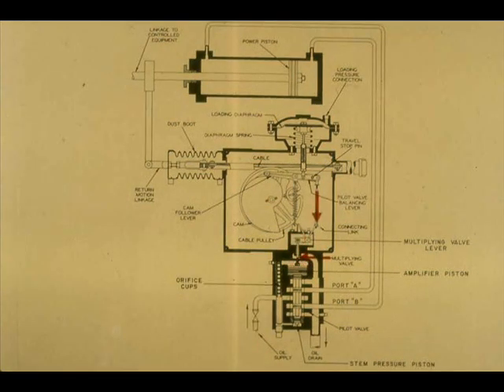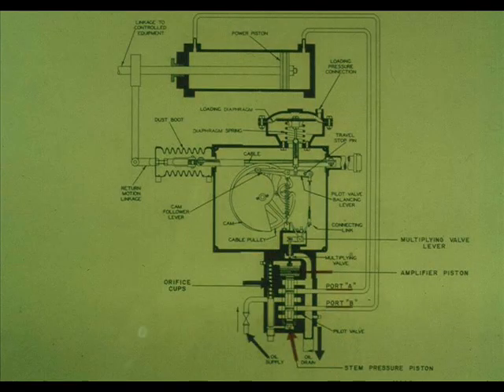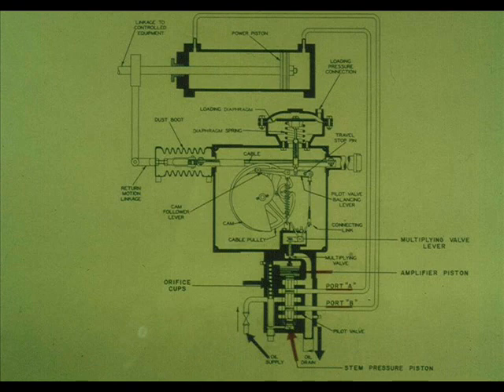If the multiplying valve lowers, it covers the nozzle, and the pressure builds up against the amplifier piston. The amplifier piston lowers. If the multiplying valve stem raises, the pressure bleeds to the drain. The amplifier piston raises because oil supply pressure is pushing the stem pressure piston up at all times.